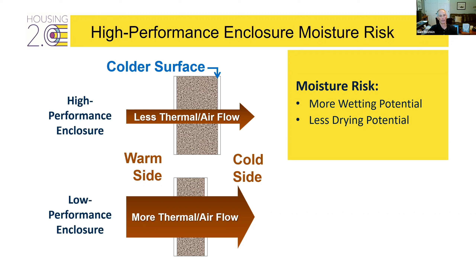And the problem is this: when you have a colder surface, you have more wetting potential. It's more likely to be at that condensation point. And at the same time, you have less drying potential because less thermal flow is now getting to the cold surface to dry it. So we have to be bulletproof, keeping moisture out of the assembly.